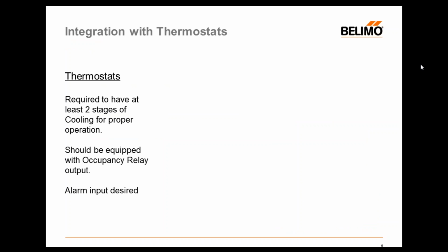Most RTUs are controlled by thermostats. Some are tied to building automation. Regardless, in order for the new economizers to work, they are required to be wired to at least 2 stages of cooling. This is true even if there's only one compressor in the RTU. The first stage will provide economizing, and the second stage allows integrated cooling. I will talk more on this in the upcoming slides.